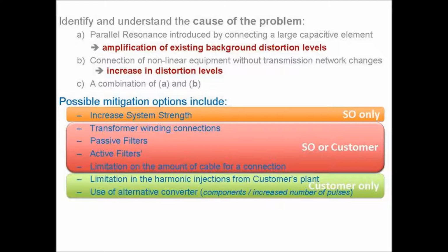So the possible mitigation options include change the system strength, obviously increase it. Transformers themselves can act as a block for various harmonics. Passive and active filters. Basically, don't install a cable in the first place, can change things and help you out. But that's not always possible, I suppose. And then limitation on the injections from your plant, so we've already talked about that a little bit. Or use of an alternative converter, so say going from 6 pulse up to 12 pulse or something like that.